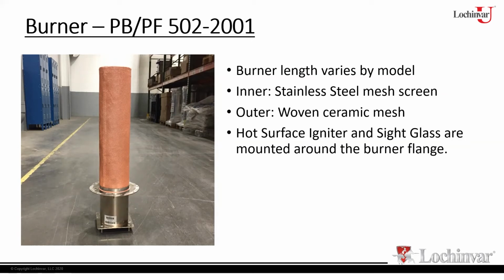Because remember, what you're trying to do with the burner, and this is with any burner, you're trying to maintain a balanced gas-air mixture across the length of the burner, all the way around in this case. So I'm trying to maintain a balance across the surface. If for some reason you put a great big rip in it at a certain point, well, the gas-air mixture is lazy, stupid, doesn't know which way to go, so it's going to go the path of least resistance, which would be through the gap. So now you would have a huge flame coming out of that gap while everything else pulls into the burner surface. And then you're going to overfire the burner, you're going to damage the burner, you're going to burn the burner up.